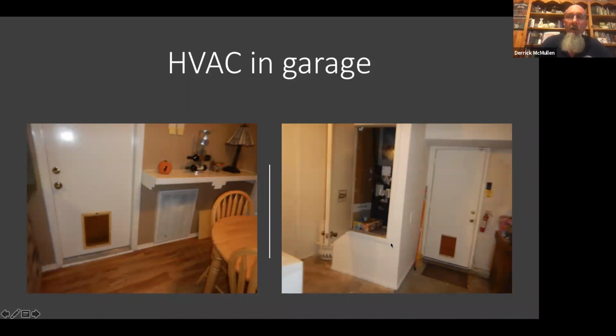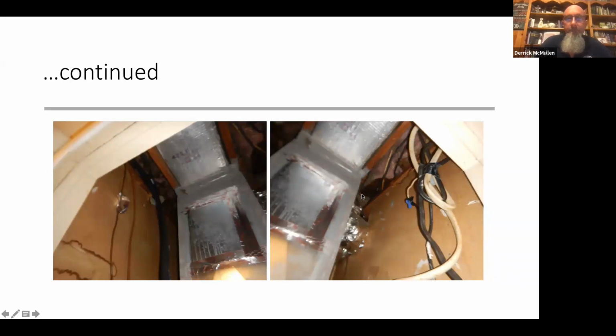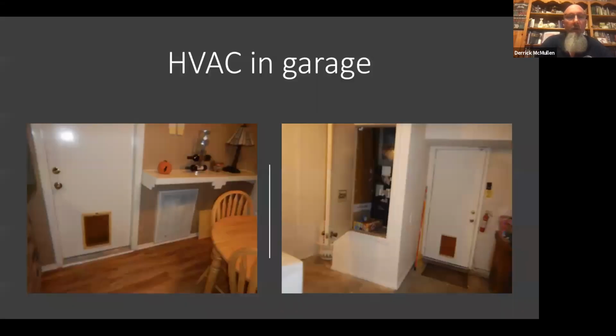One of the two. So when you have the open ceiling up there, this door now needs the same requirements as this door, because your separation has to either happen at this door opening or at the ceiling. So if the ceiling's wide open, you've got free passage of fire, carbon monoxide, fumes, smoke, and so on and so forth.